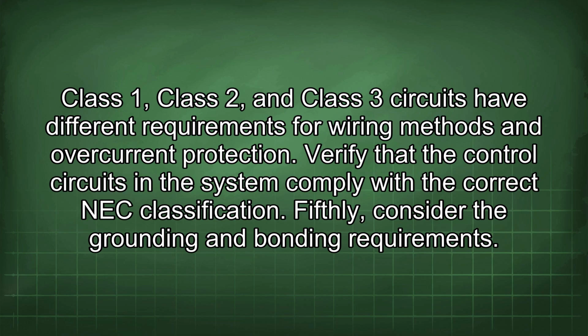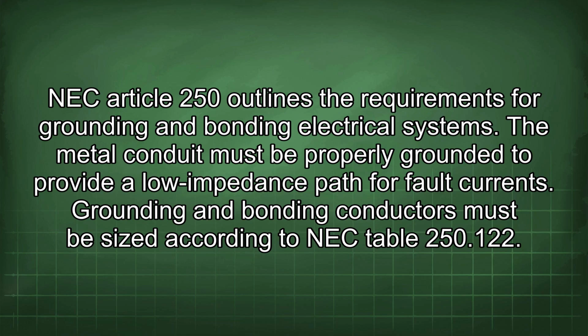Fifthly, consider the grounding and bonding requirements. NEC Article 250 outlines the requirements for grounding and bonding electrical systems. The metal conduit must be properly grounded to provide a low impedance path for fault currents. Grounding and bonding conductors must be sized according to NEC Table 250.122.